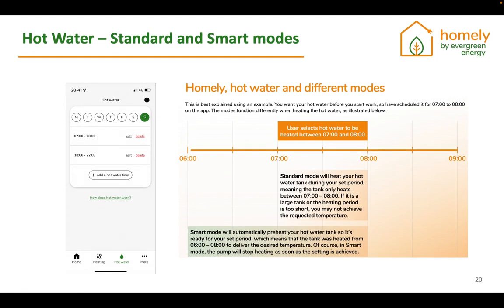With hot water, it depends on whether you're in standard or smart mode. Standard mode was created more for people who don't want the heat pump to run outside of the times that they have specified. It is very important to let the customers know that in standard mode the running costs of the heat pump might increase because they're not allowing the heat pump to run at very low flow temperatures. Whenever the set point goes active, the heat pump needs to work really hard to get to the set point and then maintain that set point. This is not ideal for the way that heat pumps work, but if it's the customer requirement, they can choose this. So that's standard and smart mode in hot water.